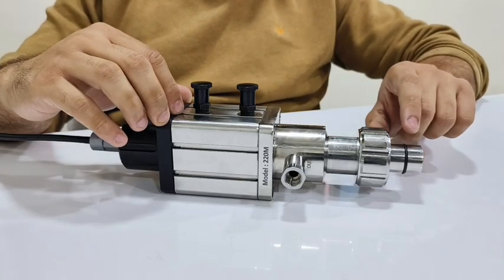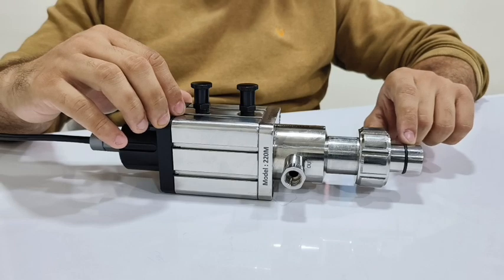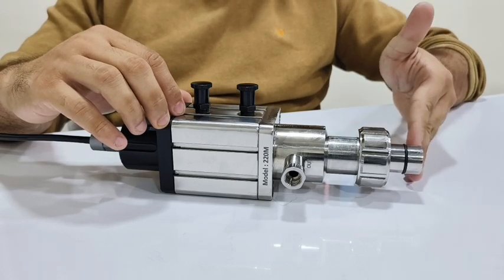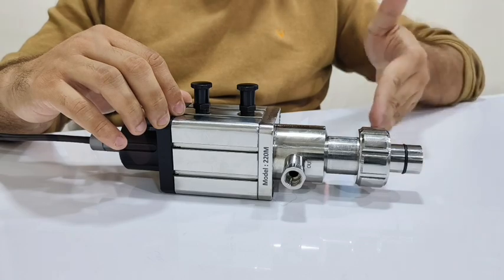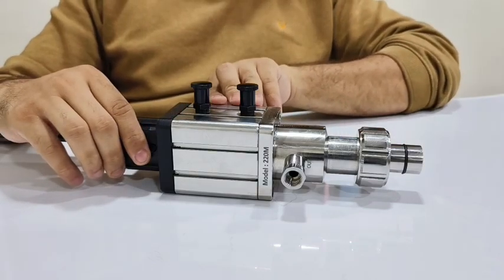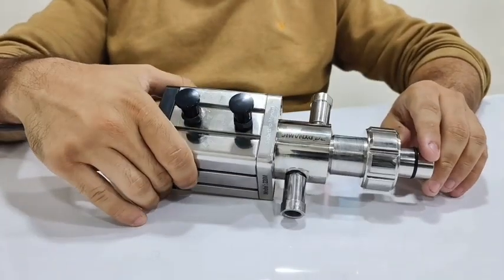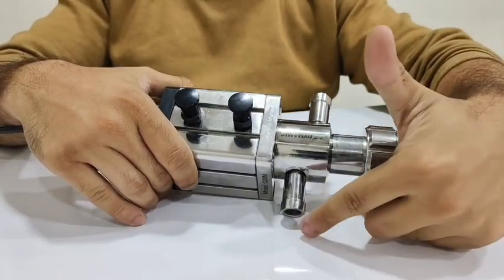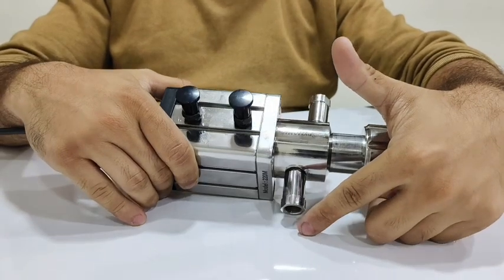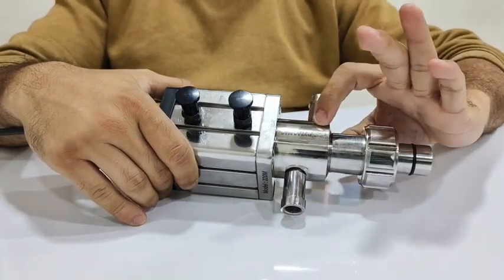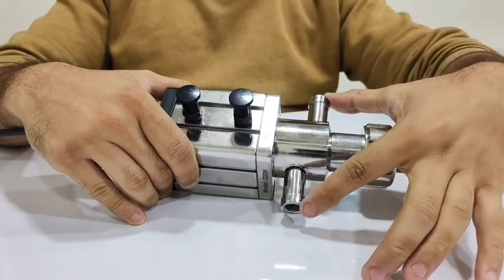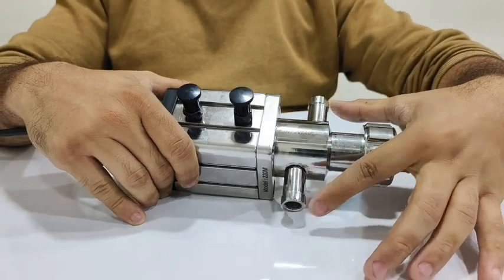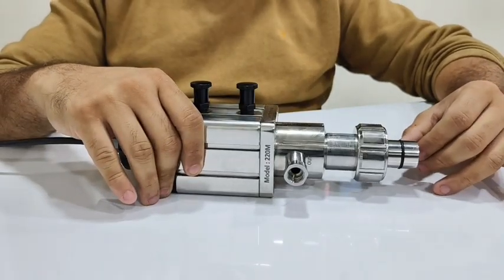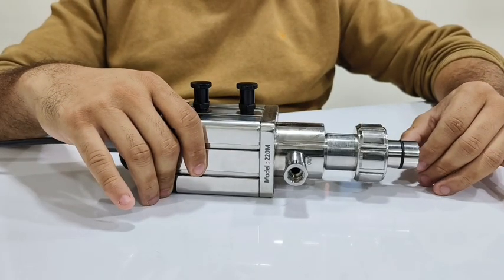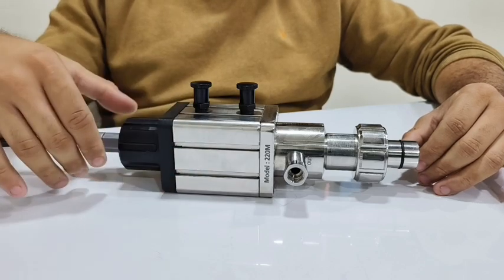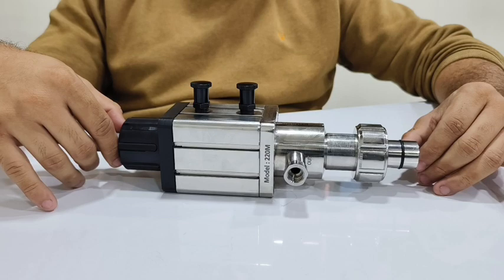There is a scraper ring and a backup sealing O-ring provided inside of this chamber, which will ensure that no reaction mass can leak out of the reactor. Now, for cleaning and sterilization purposes, as you can see, there are two nozzles, an inlet nozzle and an outlet nozzle. Through this nozzle, the opening of the flushing chamber is there. Through this nozzle, you can perform your CIP and SIP cycles. Our retractable electrode housing has an inbuilt flushing chamber which is suitable for multiple CIP SIP cycles. So you do not have to remove the electrode from the housing for cleaning and sterilization purposes.